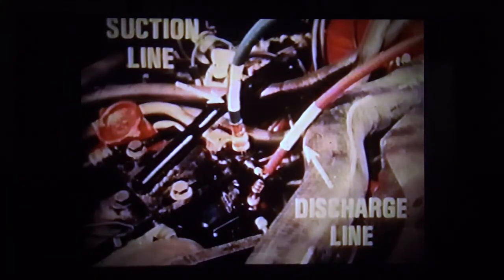Connect the manifold suction gauge hose to the compressor suction service valve port. Connect the manifold discharge gauge hose to the compressor discharge service valve port. Check to be certain the manifold suction and discharge gauge valves are closed. Open both compressor service valves one turn clockwise.